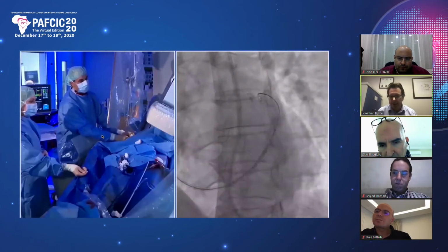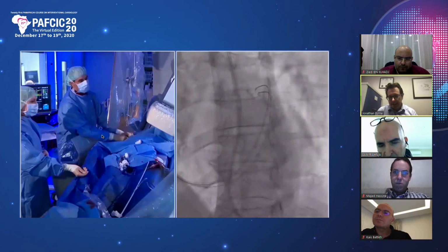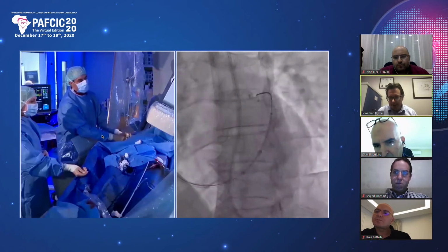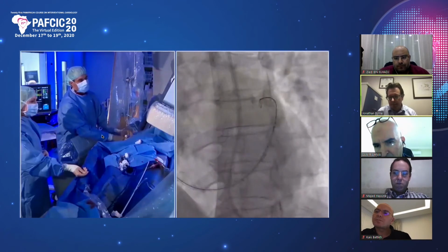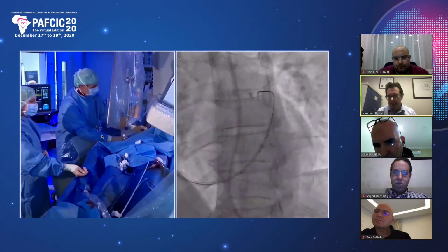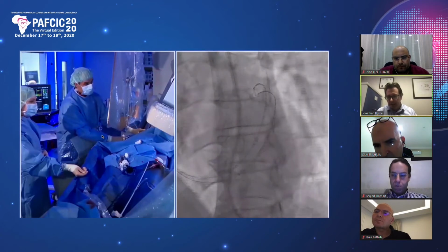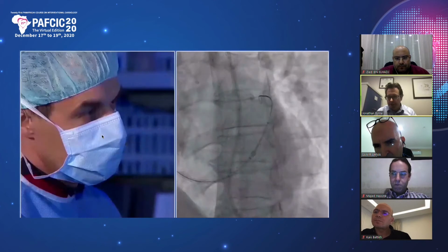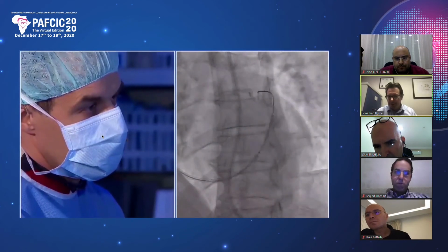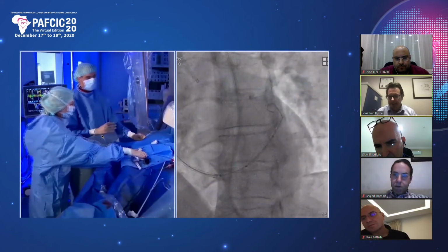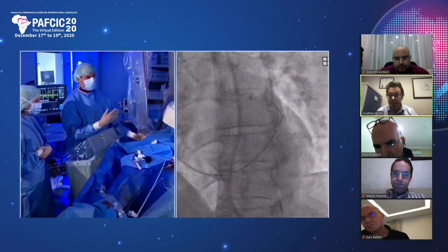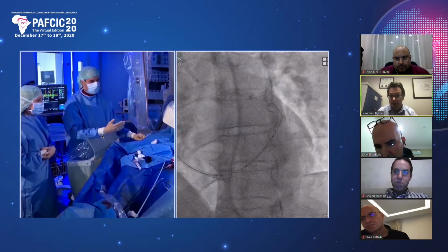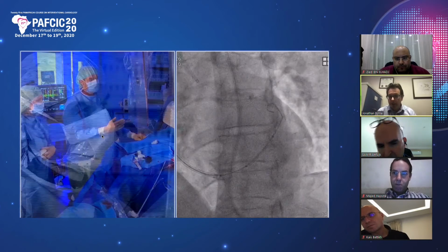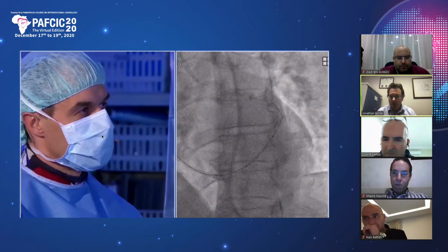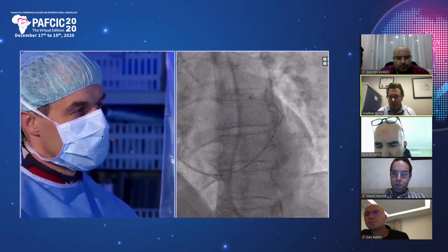your guide catheter to. Now, the key thing in deploying this device is that you always move the system and the device forward together. You should never really move the device forward if you can avoid it, and not move the delivery catheter at the same time, because the device can easily become dislodged and lost. You need to see that you are proximal with your delivery system and that the device is not moved.